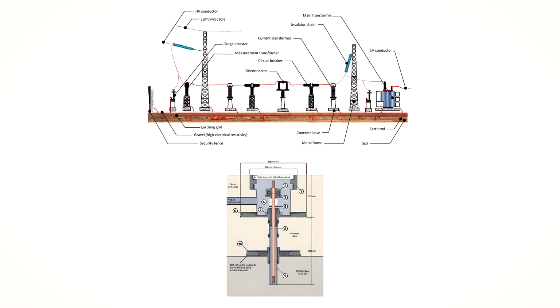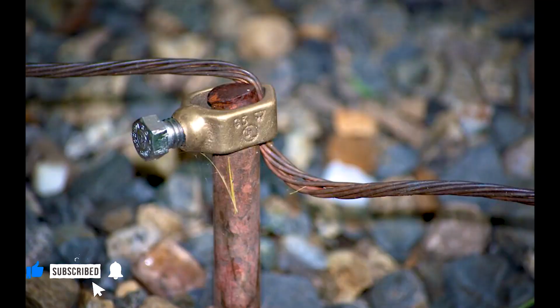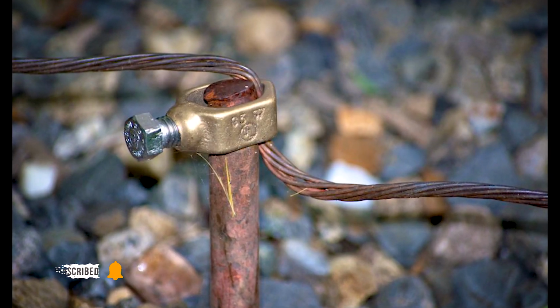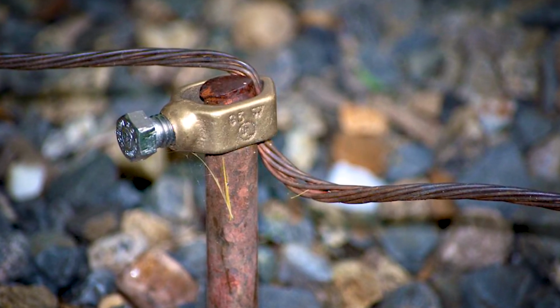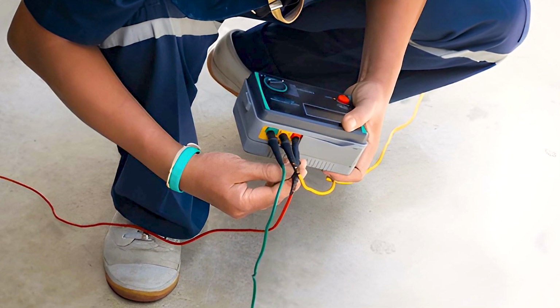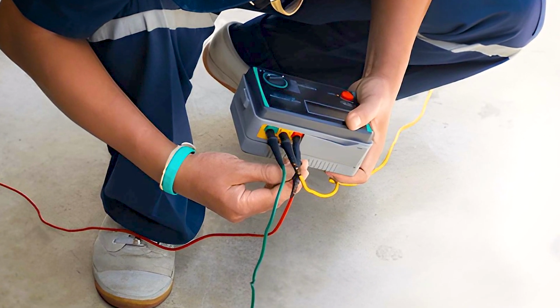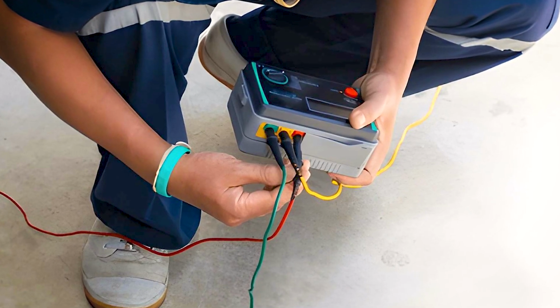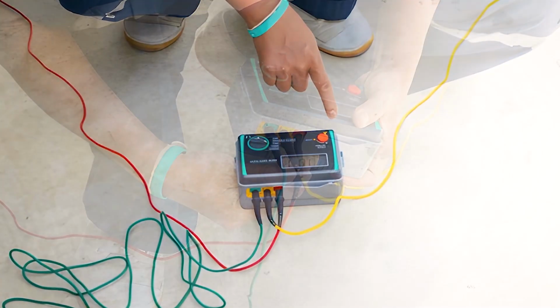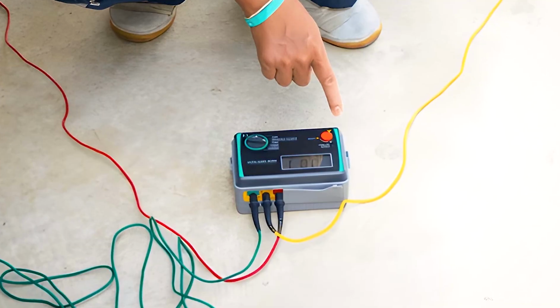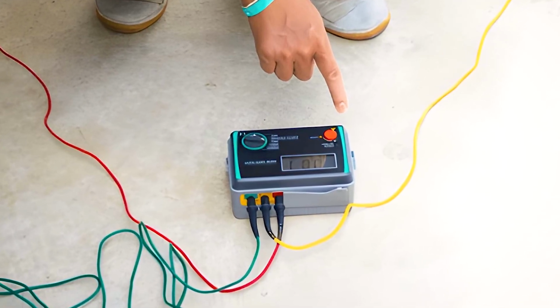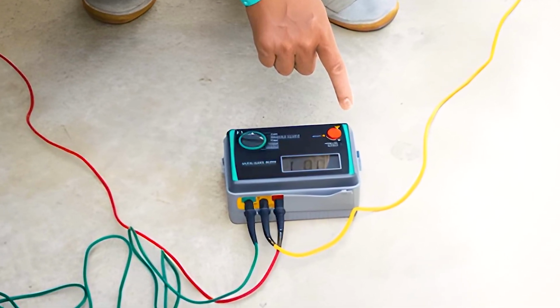However, grounding is only effective if it is properly designed, installed, and maintained. Common grounding failures, such as loose connections, corroded earth electrodes, high earth resistance, or undersized grounding conductors, can render the system ineffective, giving a false sense of safety while increasing risk. Regular inspection, testing of earth resistance, and compliance with electrical standards are essential to ensure grounding performs as intended.